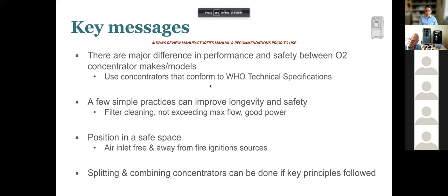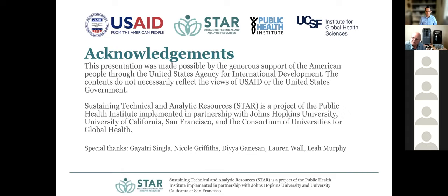So just to reiterate some of the key take-home messages, there's some major differences in performance and safety among oxygen concentrators. Make sure to be familiar with the WHO technical specifications and some of the considerations that we've reviewed here today. Always look at the manufacturer's manuals prior to using and always procure and use these with a clinician's input. A few simple practices like cleaning the filters, making sure you have good power supply, not exceeding max flow, and taking care of the device in general can really improve longevity and safety. Be careful for fire risk. And then finally, splitting and combining can be done, but make sure to follow those key principles that Robert outlined.